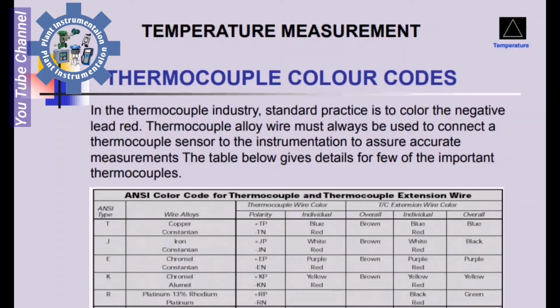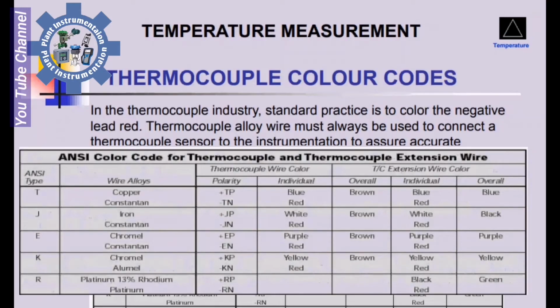Thermocouple color codes. In the thermocouple industry, the practice is to color the negative lead red. The negative lead red thermocouple alloy wire must always be used to connect a thermocouple sensor to the instrumentation. To assure accurate measurements, the table below gives details for a few of the important thermocouples. ANSI color code for thermocouples and thermocouple extension wire.